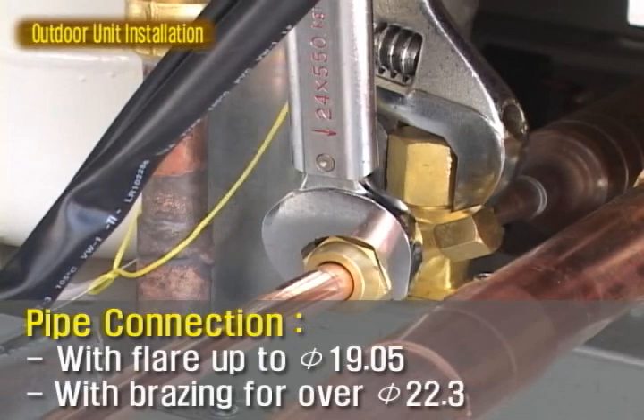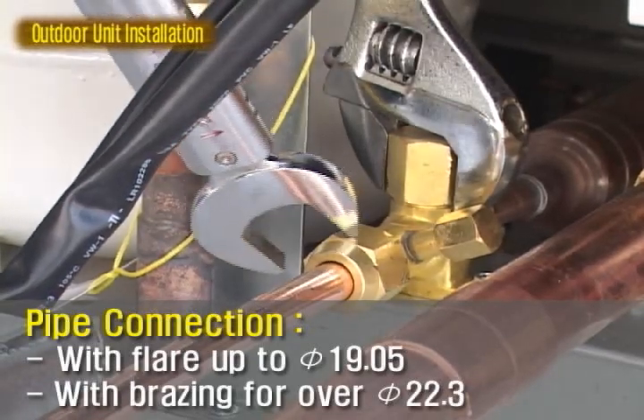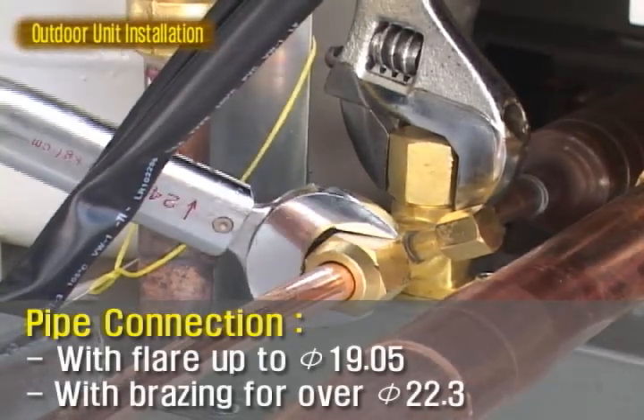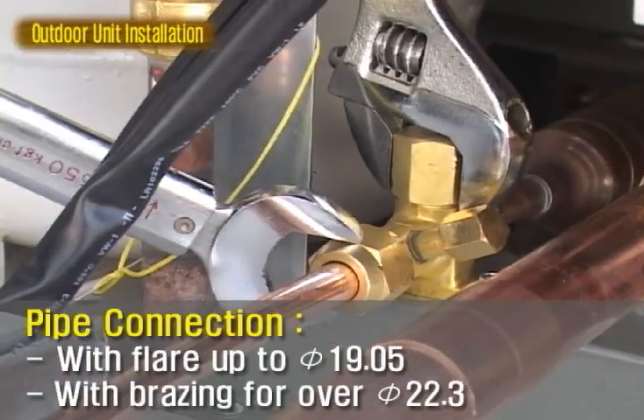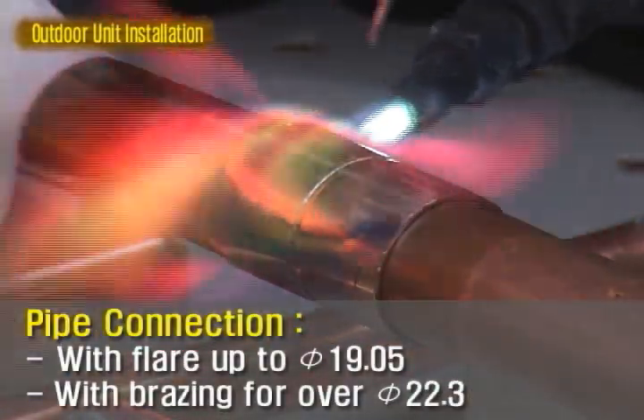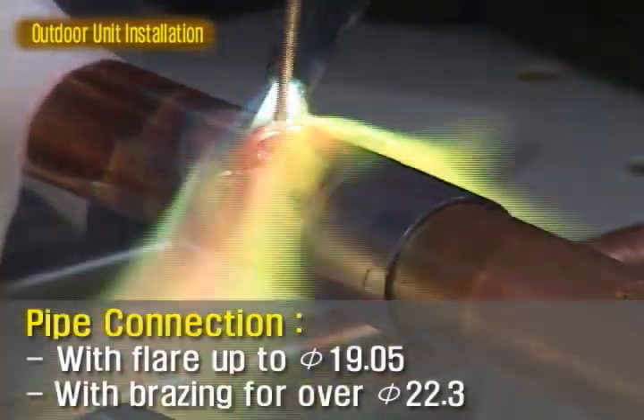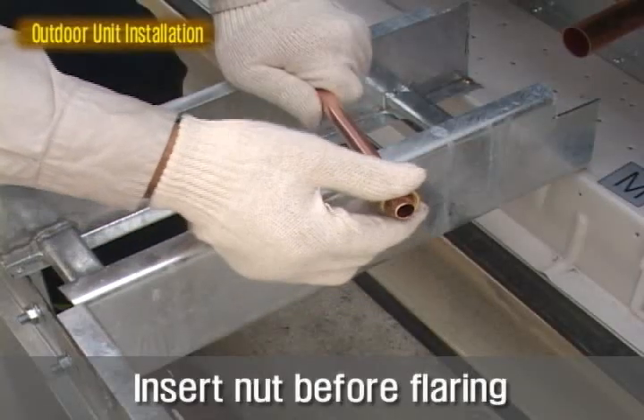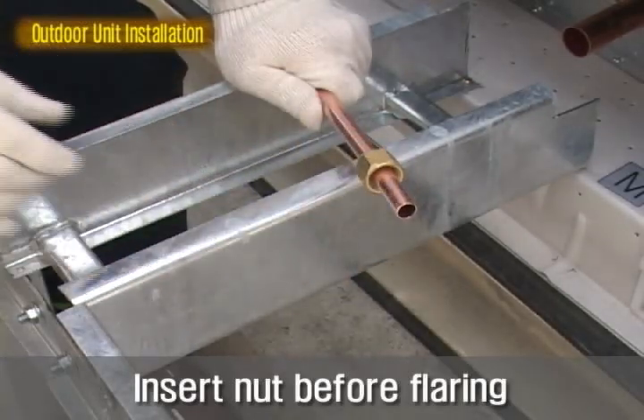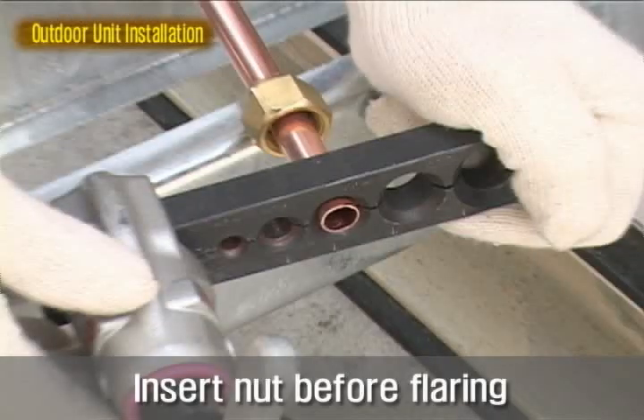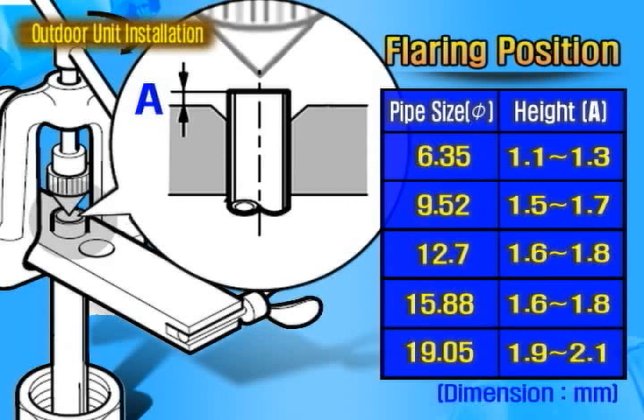Smaller pipes up to 19.05 millimeters of diameter can be flared for connection in refrigerant piping. Bigger pipes are recommended to use brazing with expansion or socket for connection. After cutting the pipe, insert the nut. Put the pipe in the flaring bar. The dimensions can differ with the size of the pipe, so flaring should be done after confirming the pipe diameter.